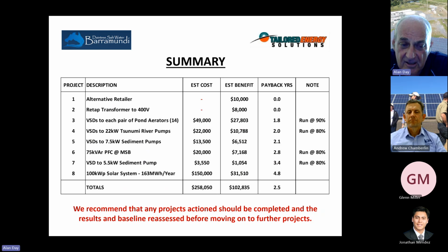And again, I've got to keep saying, you just don't do all of these, because everything you do, apart from the alternative retailer, is going to impact the baseline and potentially change the sizes and the specs of the other equipment, whether you work from the VFDs back to voltage optimization and PFC, or whether you work from both ends to the middle, or whatever you do, will have an effect and change the requirements or the spec of the equipment you would want to use.